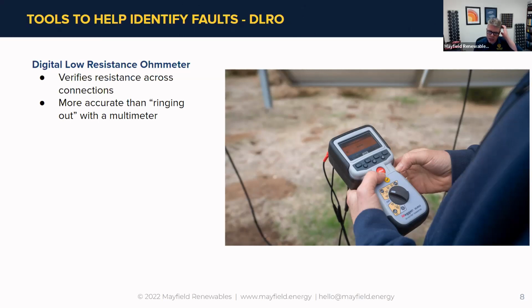Yeah. So the two things that I would bring up in terms of this test specifically, is, one is we have our UL 2703 racking systems now. And we showed that picture earlier of the ground lug, connected, somebody drilled and connected a ground lug to the back of a module frame. We're not doing that anymore. We have 2703 racking systems where the mechanical connections are making the electrical bond. And if you go and look at that spec, there is a check that in order for the racking manufacturers to pass their UL listing, to be able to stamp that as a listed product, they have to pass current from that grounding point through to the racking system.